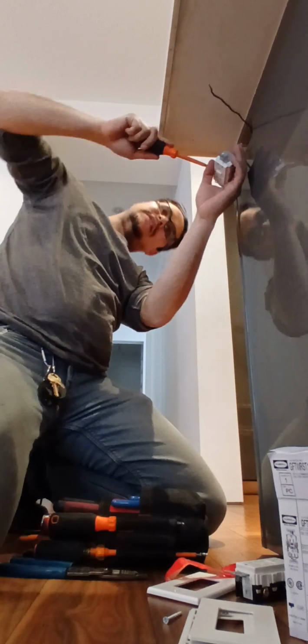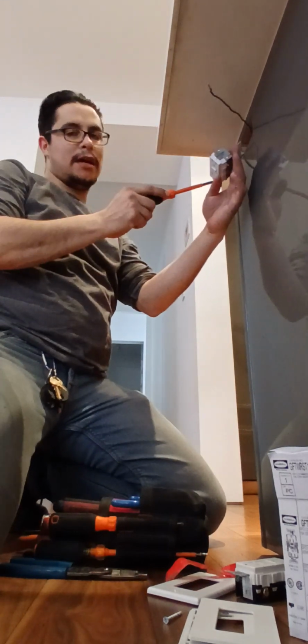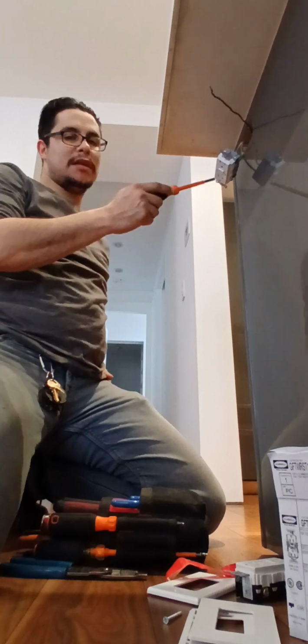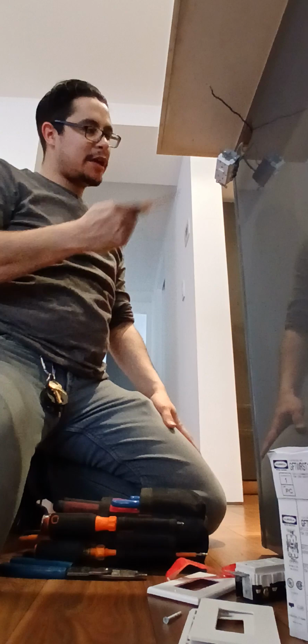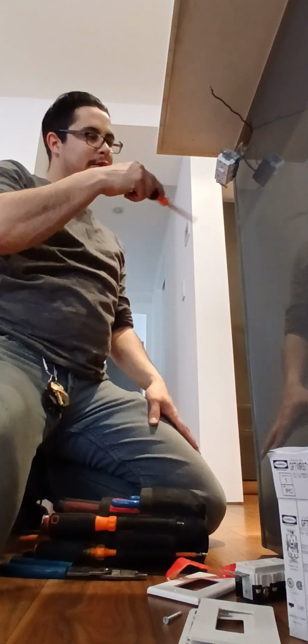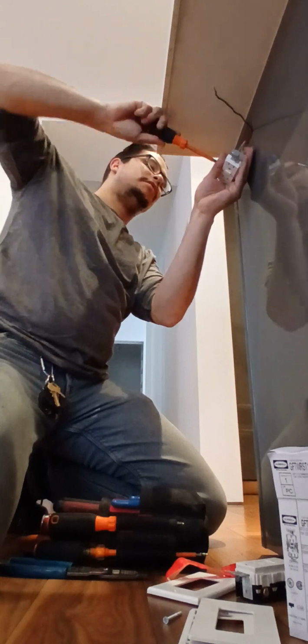So this is the line side, you want to tie the line side in. You can pigtail and just do line sides only on the GFCI to daisy chain them, or you can go into the line and into the load. It's optional.